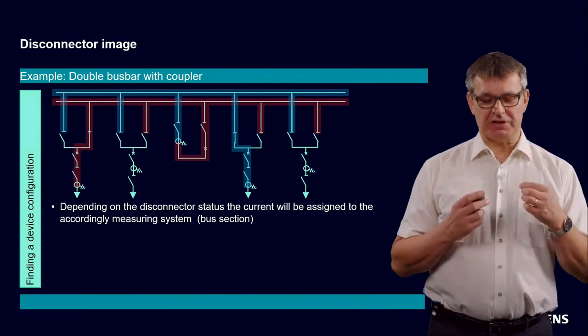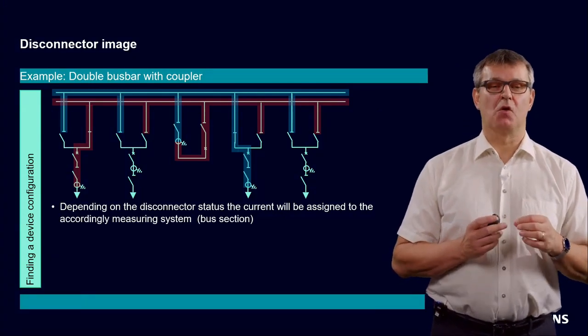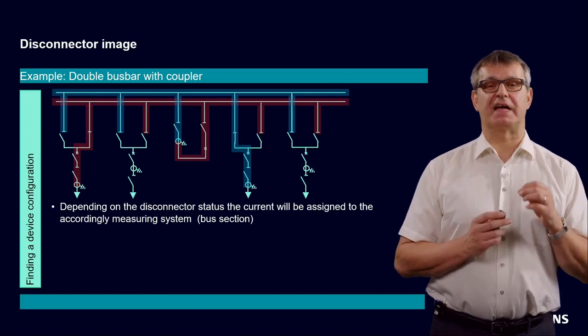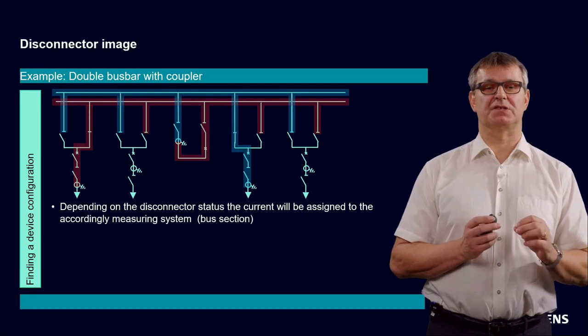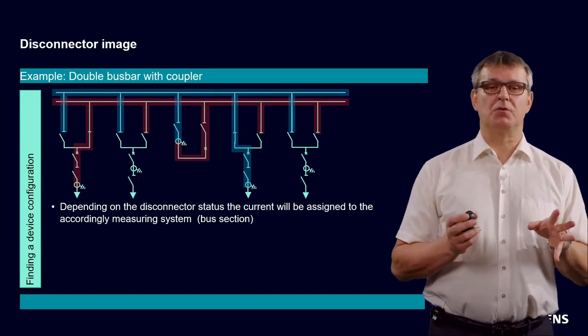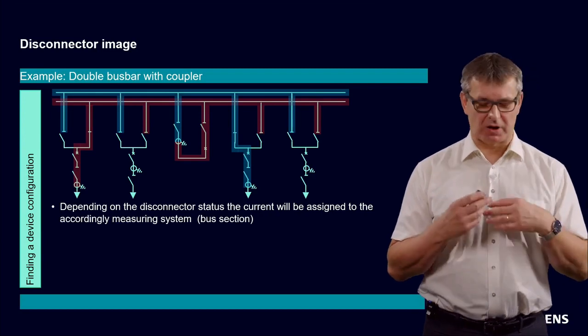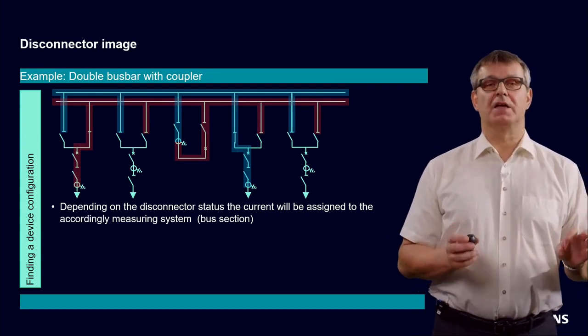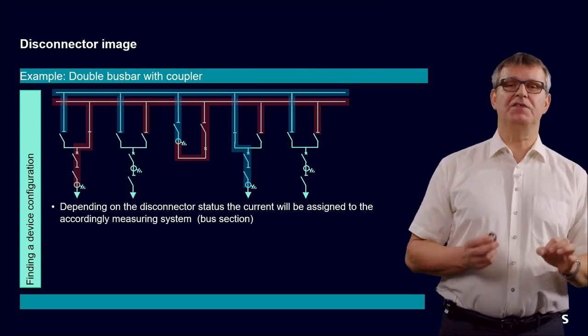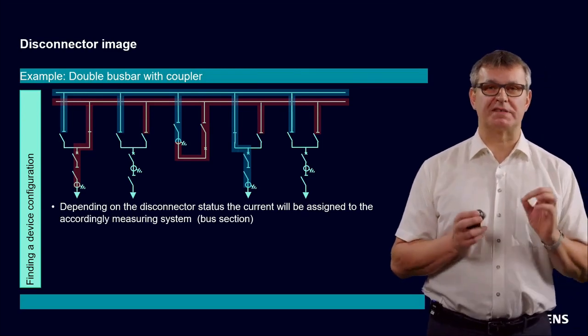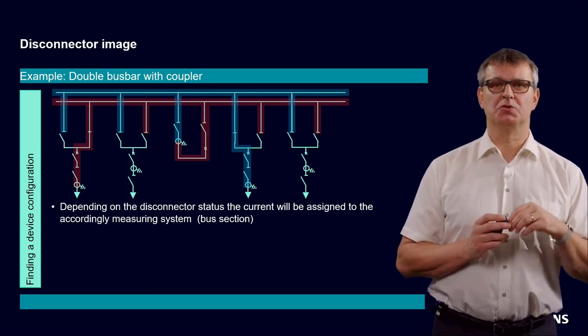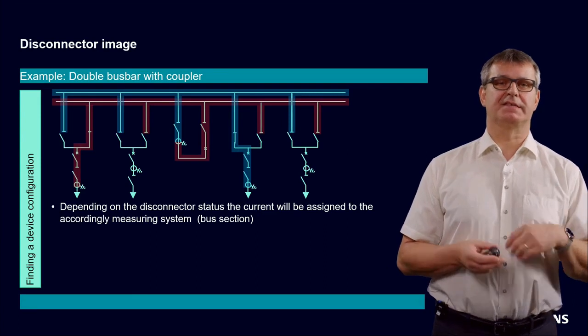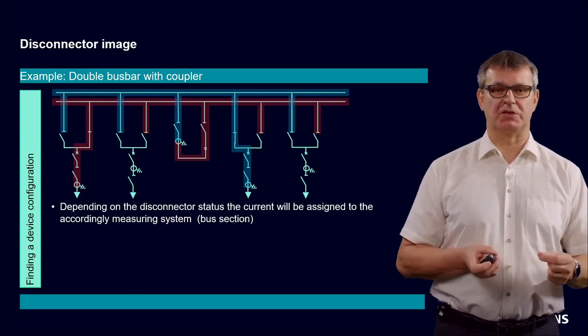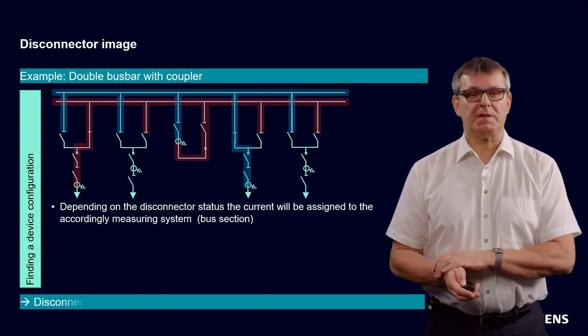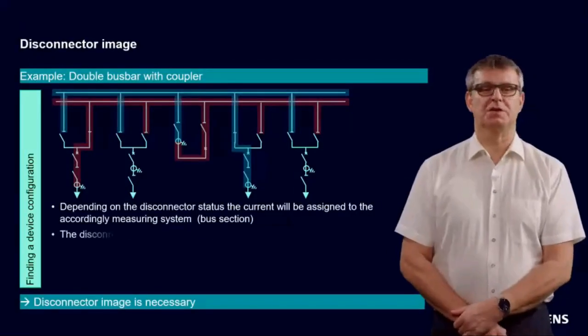This means we need a disconnector image every time a feeder current can be assigned to different bus zones, to different bus sections. So if you want to answer these questions, don't look at whether you have any couplers. Couplers don't matter. Do we have one feeder, and one feeder is enough, where with disconnectors we can assign the current of this feeder to different bus bars, to different bus sections? In this case, we need a disconnector image. So in our case, don't forget, we need a disconnector image.